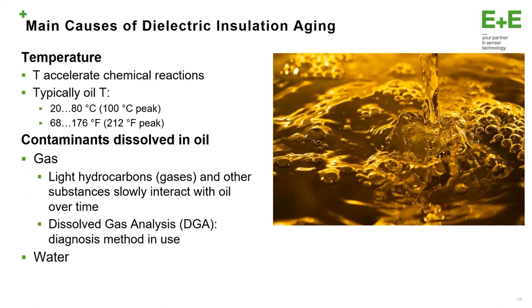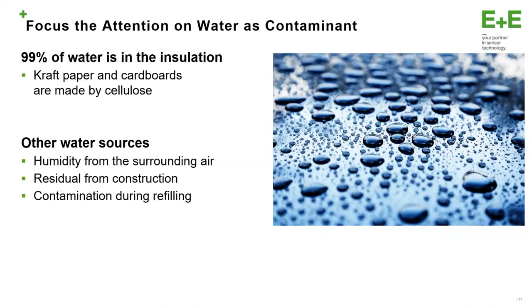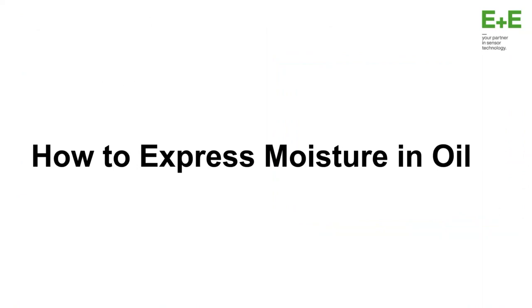The other main source of aging is water. We focus our attention on water as a contaminant, because 99% of the water is already inside the insulation layers, because they are made by paper or cardboard which are made by cellulose. Other sources can be some contamination during the refilling process, or humidity from the surrounding environment — maybe there is some leakage in the tank and not adequate sealing — or there can be some residual from the construction.